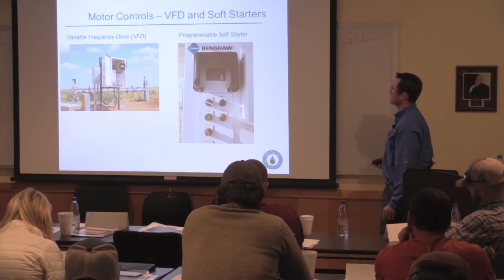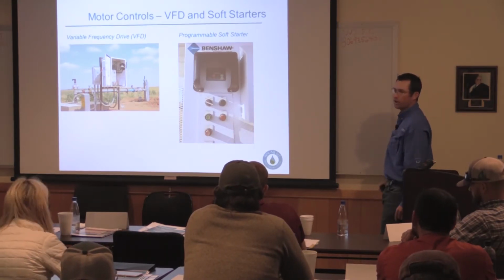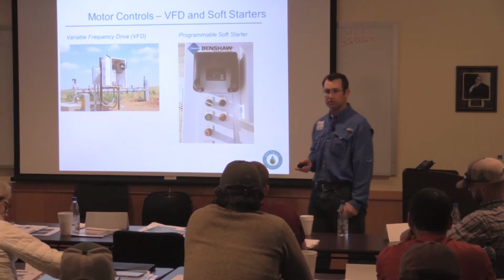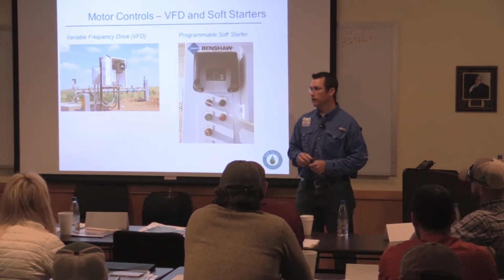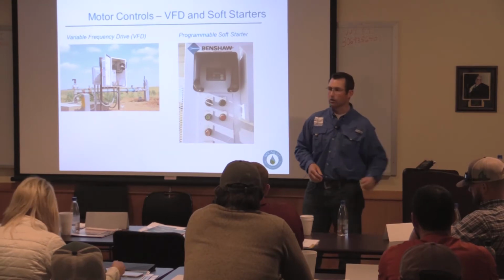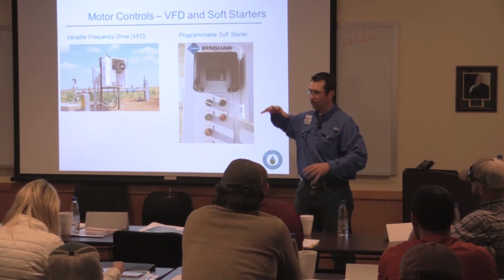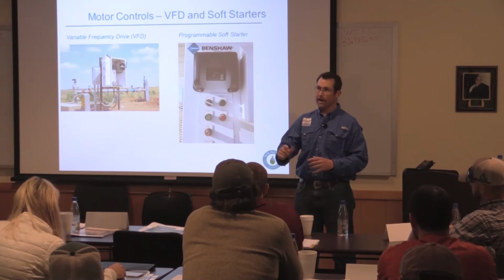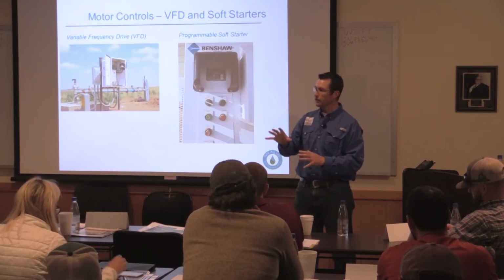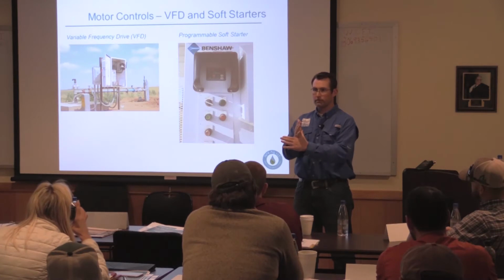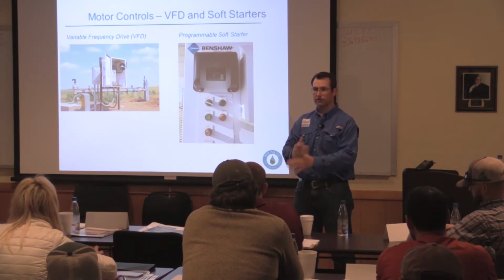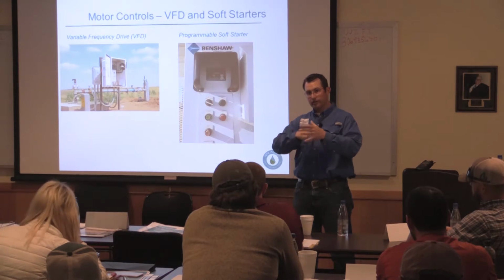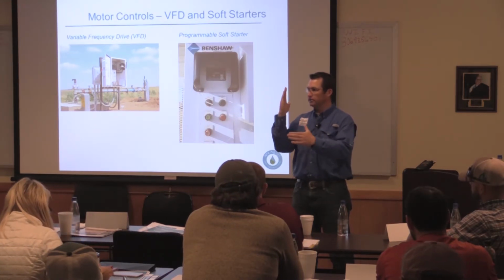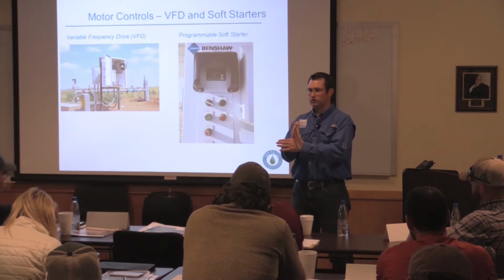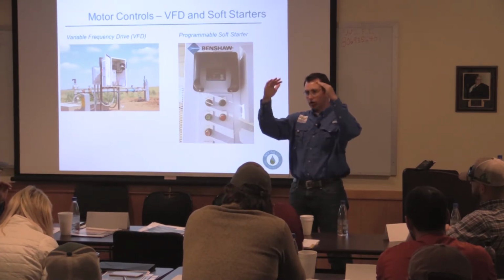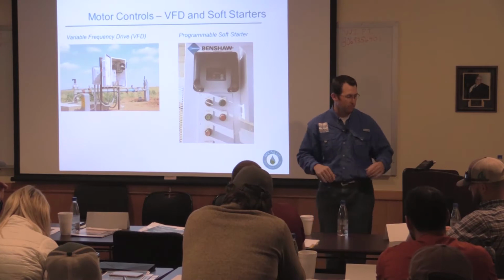So we'll look at motor controls, VFDs and soft starters. These are pretty mandatory on a genset, exactly for the point that was discussed previously, which is inrush current. When you start an electric motor across the line, it hits hard. Okay, so it's going to give everything it's got, and the amps spike almost infinitely. Think of that motor starting as a short. Okay, the hit is so hard on the service line because that motor's going from static to dynamic. When the electric hits it, it basically is hitting an across the line short on the motor. And then once it starts spinning, the current comes down and it starts to reach its equilibrium.